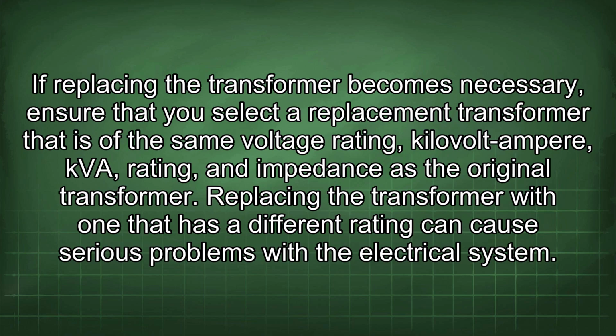If replacing the transformer becomes necessary, ensure that you select a replacement transformer that is of the same voltage rating, kilovolt-ampere, kVA, rating, and impedance as the original transformer. Replacing the transformer with one that has a different rating can cause serious problems with the electrical system.